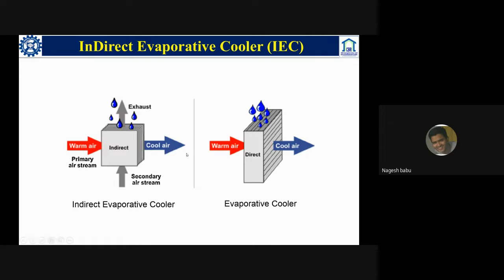Now moving to indirect evaporative cooling. As we have discussed, that was direct evaporative cooling. If we are using indirect evaporative cooling, instead of a single stream, we separate the stream into two streams, a primary stream and a secondary stream. The cool air moves to another heat exchanger, where it transfers its coldness to the other stream, the primary stream. That is how cooling happens in an indirect evaporative cooler.